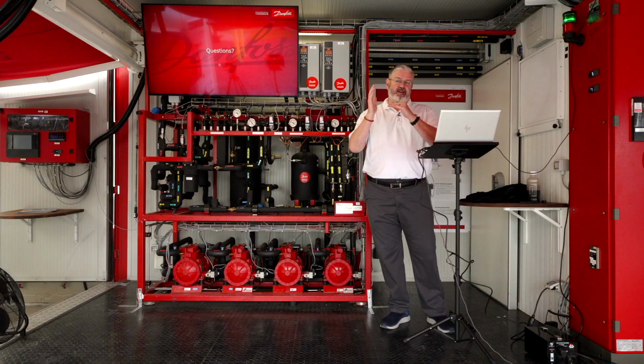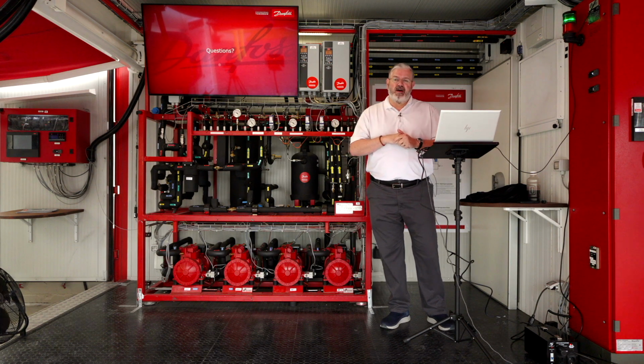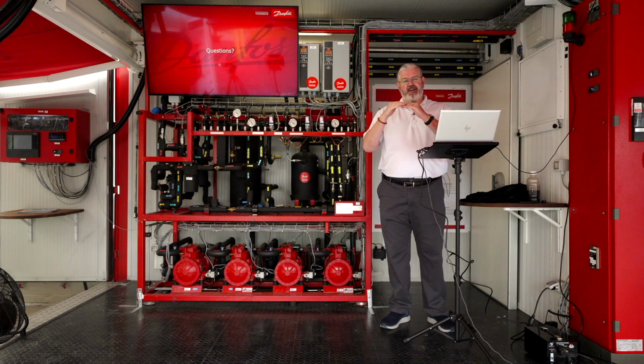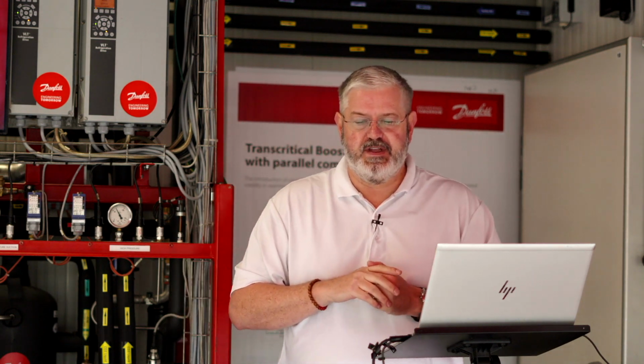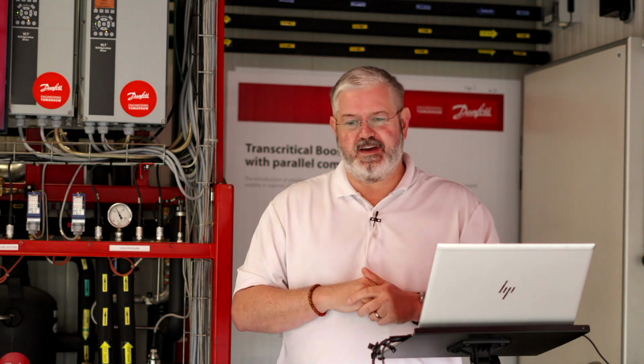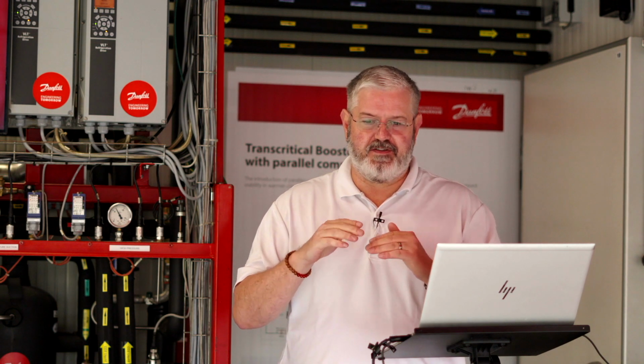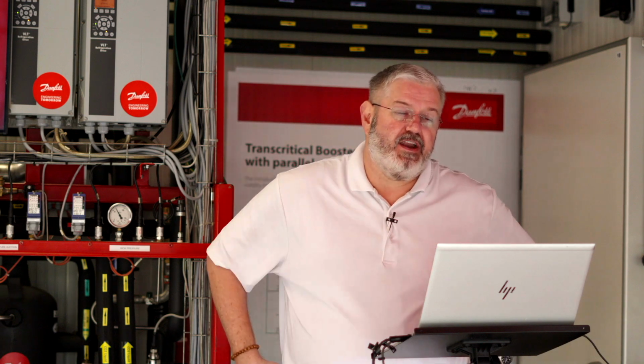I can't stress enough that the vent valve doesn't just pop open and vent the entire charge. It pops open until the pressure on the downside, until system pressure gets below its rating, and it reseals. So it kind of burps. It makes a chattering noise, but it's going to just burp slowly over time. My guess would be that you'll lose charge during the day, and then like this system, it's fully charged. We closed it up overnight, 70 degrees. It didn't vent anything. You're not going to lose your charge all at once, which I think is a common misconception because the valves kind of burp. I don't want to say an actual time because I don't want to be held to it later.